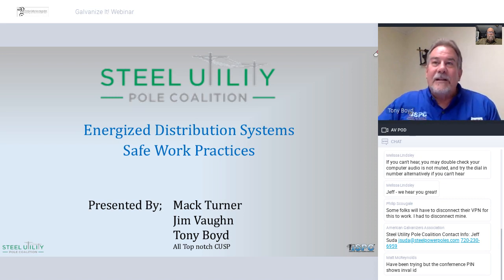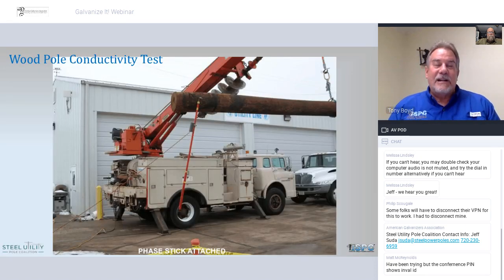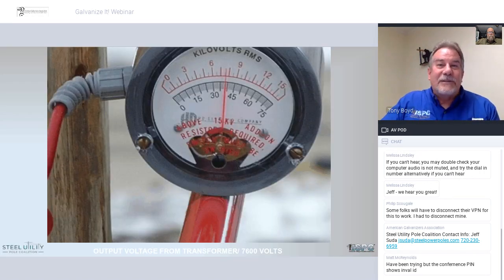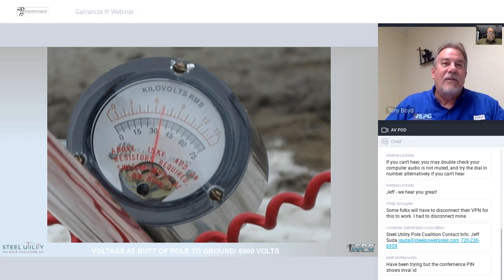To get started, a couple of slides that I showed last time, to re-emphasize the difference between wood poles and steel poles. Steel offers a little bit better conductivity than wood does. This was a test done in Nebraska. We had a Southern Pine 40-foot CCA treated pole suspended from two digger derrick trucks. We put lag screws in each end, and on the top we energized it with 7,600 volts. We backfed through a transformer and energized the top of the pole, and to no one's surprise, we got 6,900 volts at the bottom of the pole.